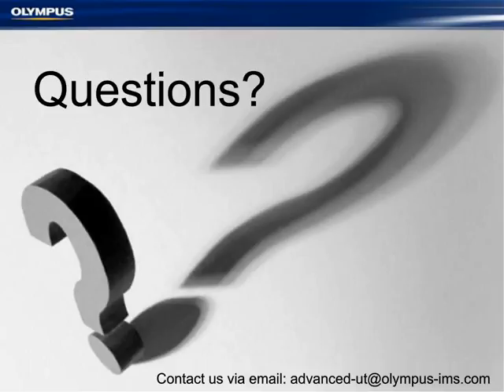They're asking, what are the drawbacks, or what would stop me using it in day-to-day vessel inspections? Okay, well, I see some of the limitations that people normally do. The biggest one is implementation. You have to figure out the codes, write new procedures, and have trained personnel, all these things. This is the biggest obstacle for advanced ultrasound, people, as with anything new, right?